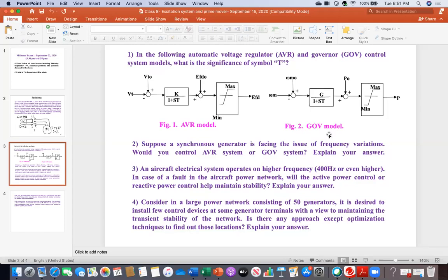No, excitation control is this one, AVR. If we see figure 2, there is speed, omega m. So, speed, and the last product, the final product, is the mechanical power. So active power means active frequency control. If you see Ns = 120F/P, speed is related to frequency. Pole number is fixed in a machine, but frequency and speed change. So this means you have to use the governor, because frequency variation means if you control the speed, then the power will be controlled, and that will fix the frequency.